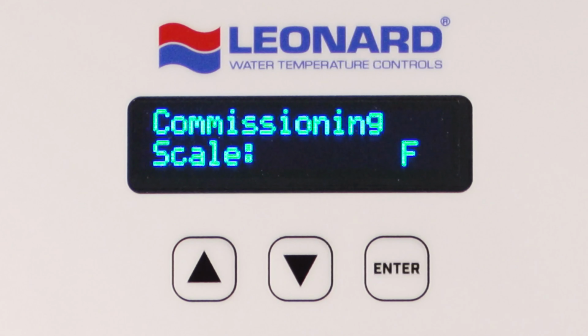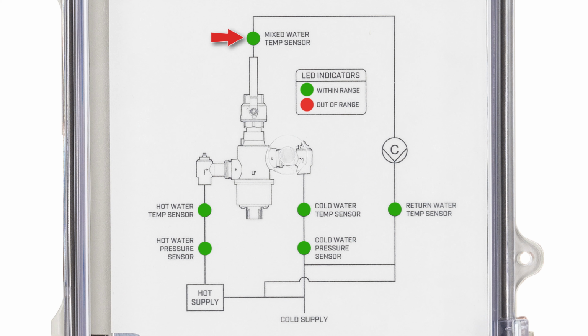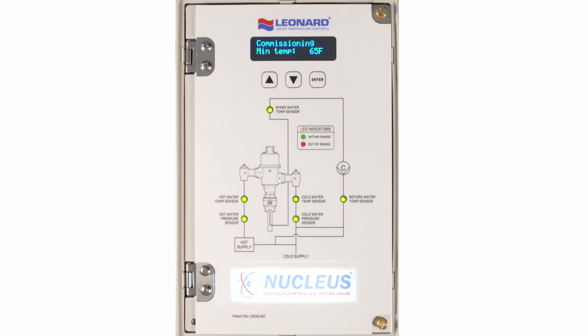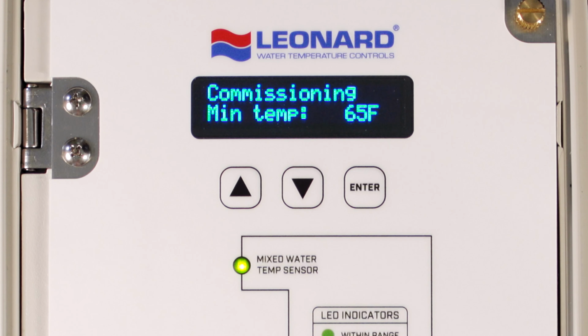Commissioning menu screen 3, minimum system temperature. Pressing down 2 times displays min temp. This is minimum alarm temperature as measured on the primary outlet temperature sensor of the Nucleus mixing valve RTD T3. Measured values below this value will cause an alarm condition that will switch a relay to normally opened. See O&M manual for the alarm relay detail. Default value is 65 degrees Fahrenheit.